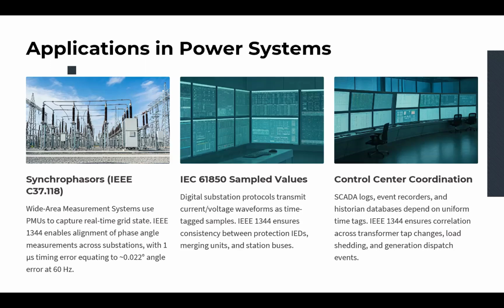or inter-device communication becomes consistent. Now, IEEE 1344 basically provides the precise shared time base so all the devices can use it as a reference. It defines how you have to tag samples, how to ensure the traceability of the synchronization, and how to detect if you lost the synchronization. Without the criteria defined in IEEE 1344, the time coordination of sample values would be temporally misaligned, which basically means false trips, missed faults, or relay malfunction.